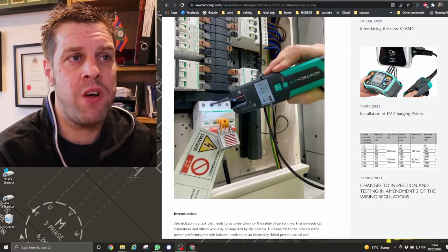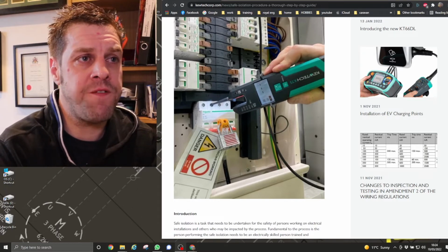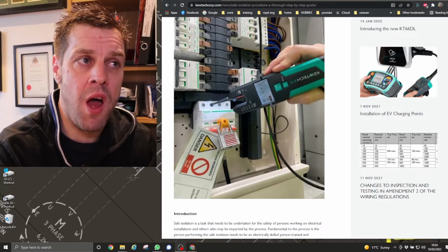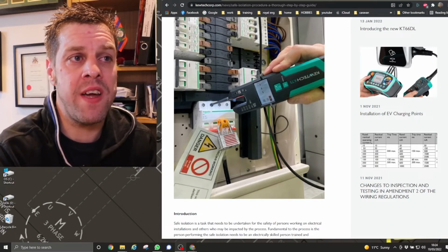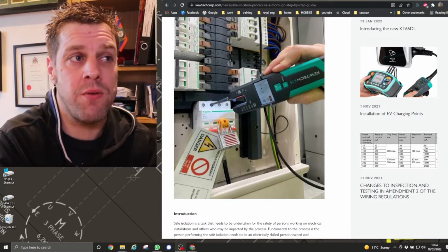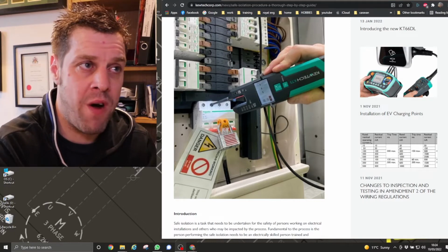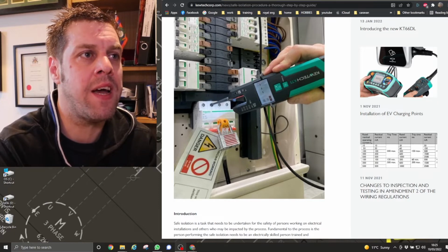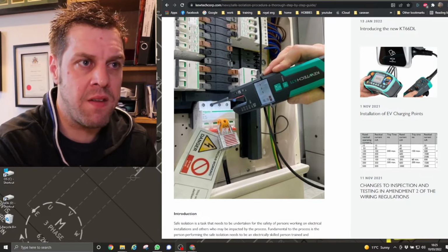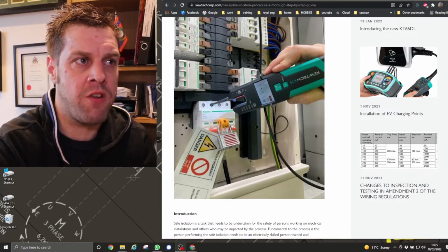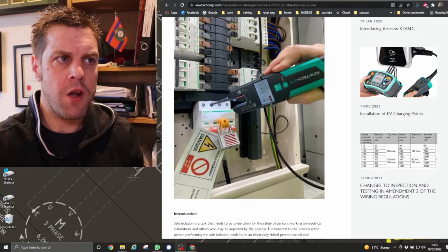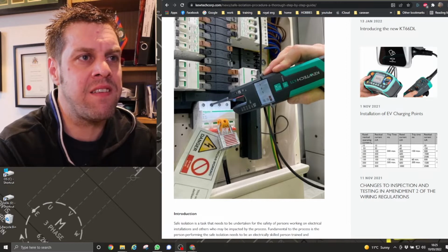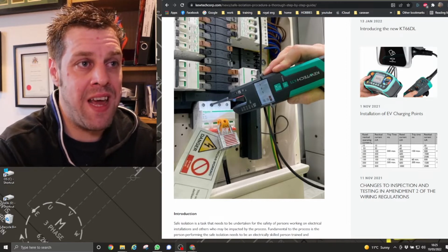So now we're in the situation where someone's on the final stage of their safe isolation, checking these terminals, but we all know, really, that below this, the terminals are live and they're exposed. They might be IP4X, whatever it is, but they're exposed also in this massive hole here. What horrors lie beneath? Are there open busbars? Are there lugs coming out? Tails for lugs, metal bits? Unisolated things. Someone could isolate there with that lock off.